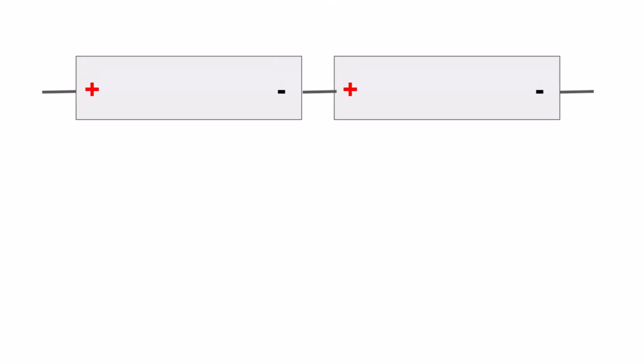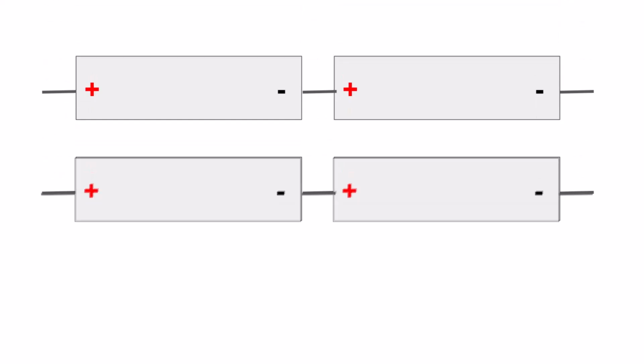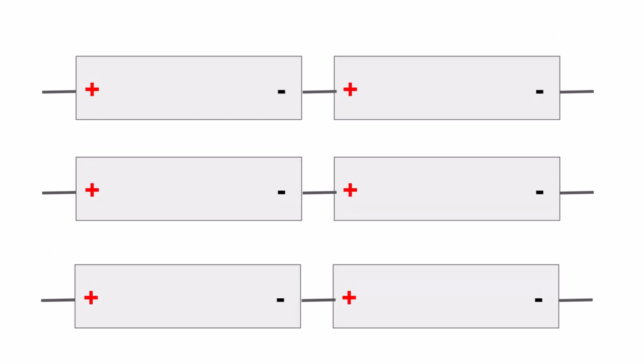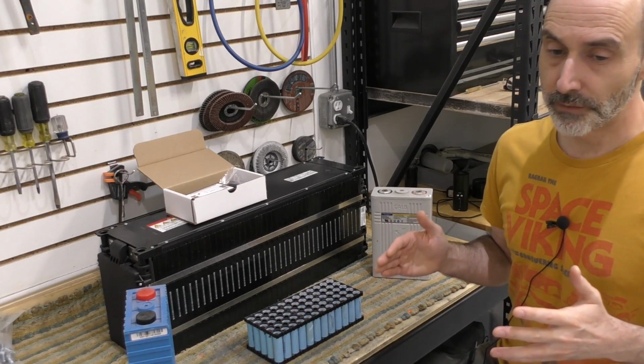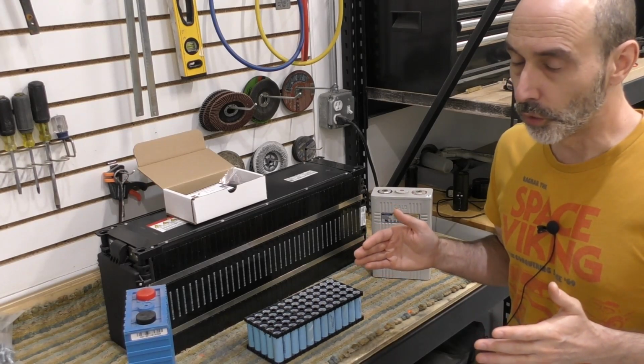That means creating 3 independent 172-volt packs and then paralleling those. Now, as I explained before, the downside is when you parallel high voltage, if there's any imbalance in the modules, it creates eddy currents between the higher voltage and lower voltage modules. Those eddy currents could be tens of amps if you're off by even a tenth of a volt.